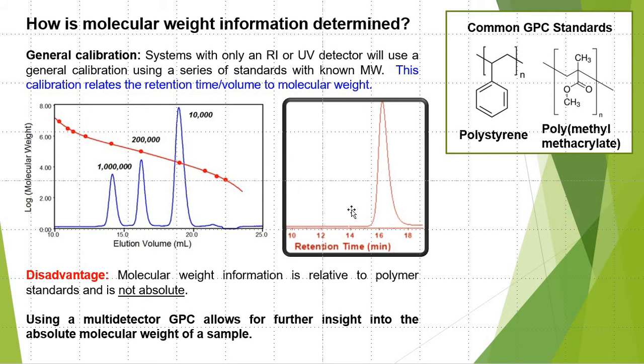Then when you go to run an unknown polymer sample, as shown here on the right, it'll relate its retention time to the calibration curve created earlier, and you can get molecular weight information such as number average, weight average molecular weights, and polydispersity.